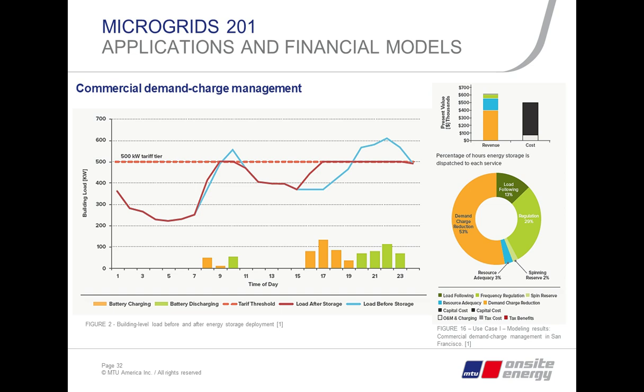So this is another really good application: commercial demand management. What we're looking at is a customer with a tariff, in this case about 500 kW, and anytime they go above that, the utility sets their price for the next 12 months. So the idea is always to stay at or below that tariff. Like any normal commercial building, you'll have differences in load throughout the day. In this case, you can charge the battery in the morning, discharge it at the peak, maybe right before lunchtime, charge again after lunch, and discharge again in the afternoon, always making sure you're at or below that tariff. As you can see in the column on the right, it gives you the revenue and the time that each of those value stacks is available to the battery in this application.